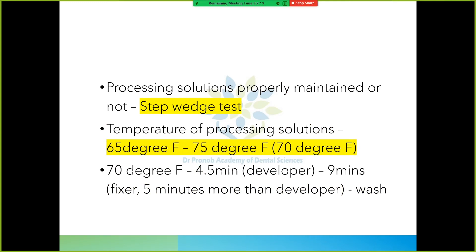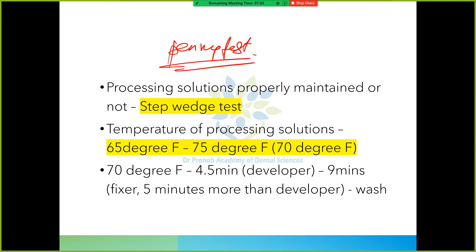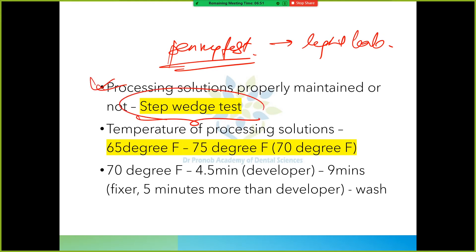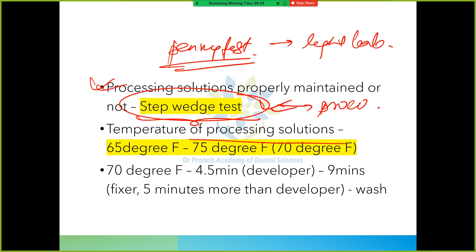We have studied the penny test - it is used to check for light leaks. There is also another test known as the step wedge test, which is used to check if the processing solution is properly maintained. The temperature of the processing solution should be 65 to 75 degrees Fahrenheit, with an average of 70 degrees Fahrenheit.